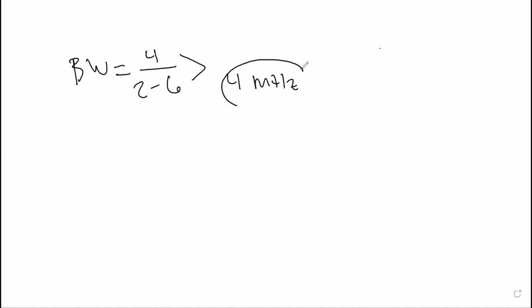So here's how it goes. My bandwidth is my range of frequencies. So here's my usable frequencies. Like for our machines, we use like say 2 to 5. Oops, I lied. Let me go back. So we're using a 4 megahertz, and our machine can read a 2 to a 6. So our bandwidth would be 2 to 6, so 4 megahertz. Our bandwidth is 4 full megahertz worth. So I can work in a 4, a 3, a 5, and I can work in partials of those too, 3.5, 5.5.